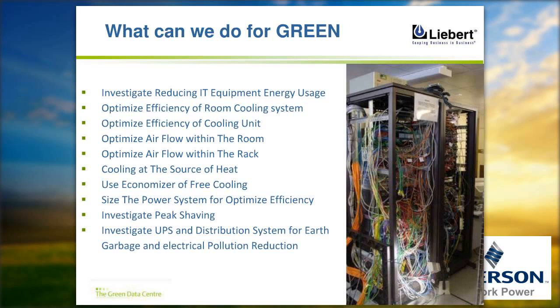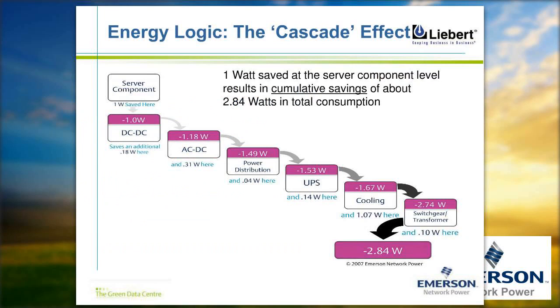Our approach starts right from how you select the IT devices for a data center. Maybe when you are buying for the future, you may want to specify certain elements which will help you reduce the IT consumption of that computing device, however not compromising computing. Now, if you look at how it helps to reduce the facility load by selecting reduced consumption on the IT side, 1 watt saving at IT can yield almost 2.8 watts at the facility level. Because everywhere we are converting this power from one form to another form, and another form to a third form, till the time it reaches the server inside.